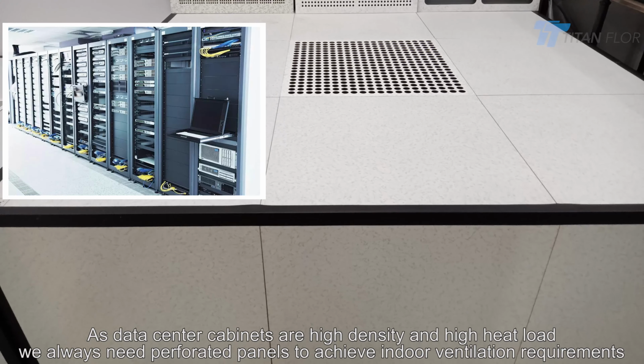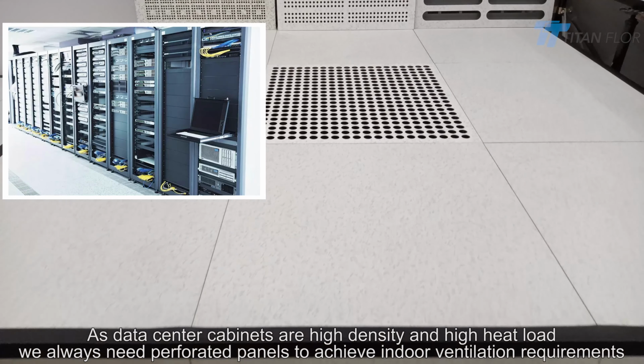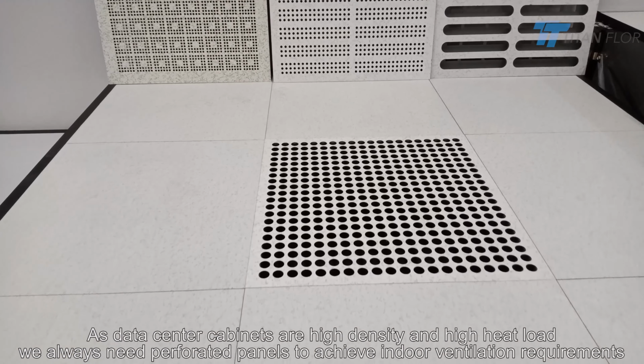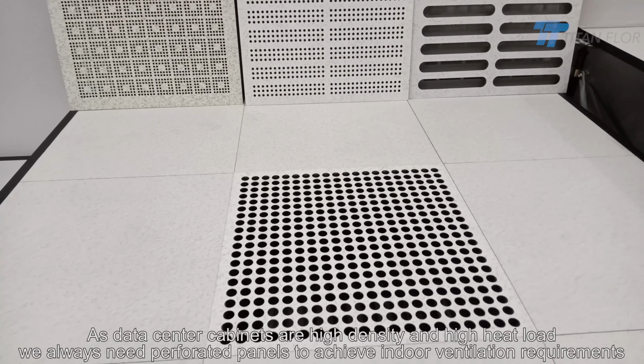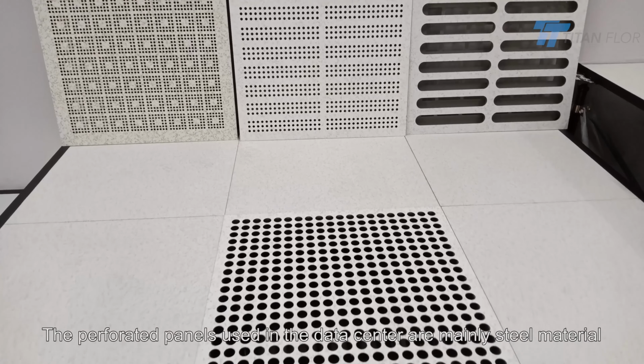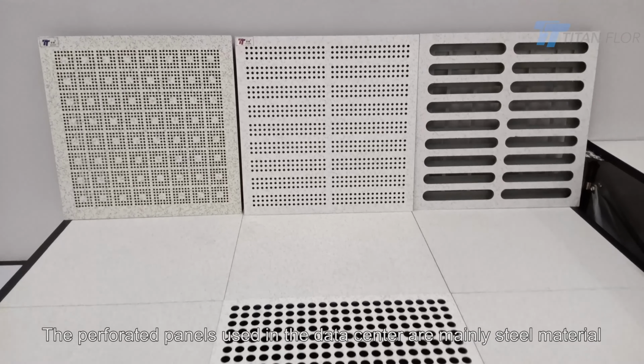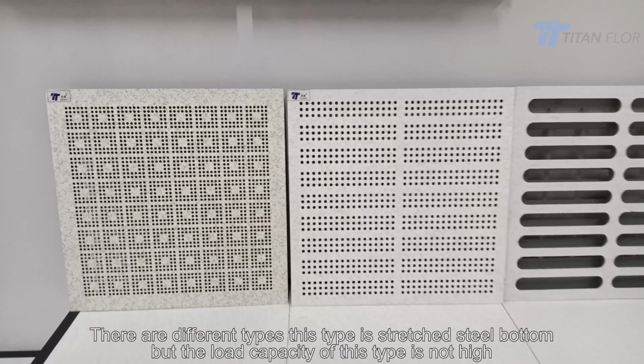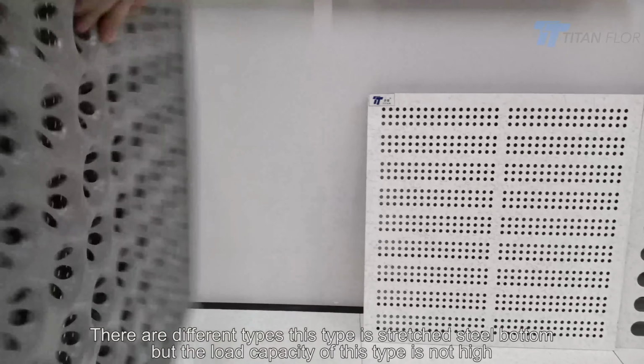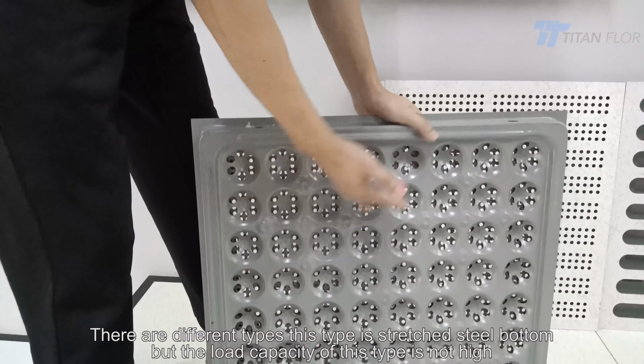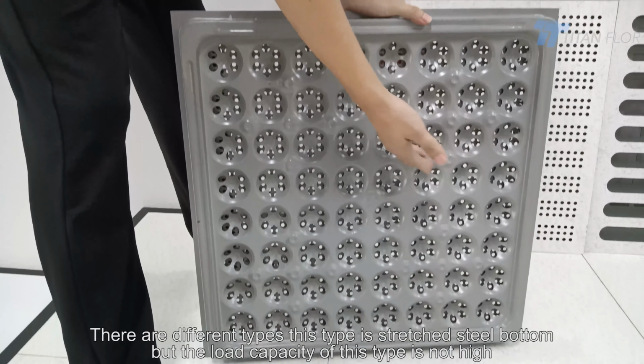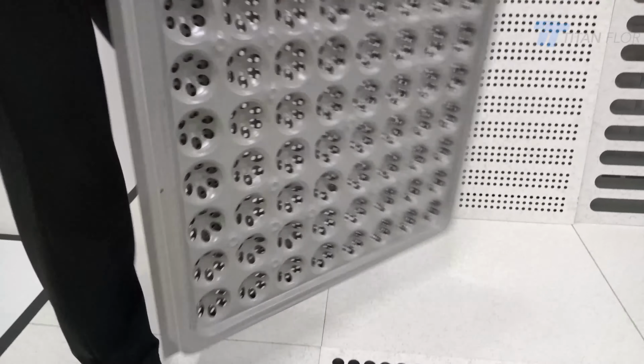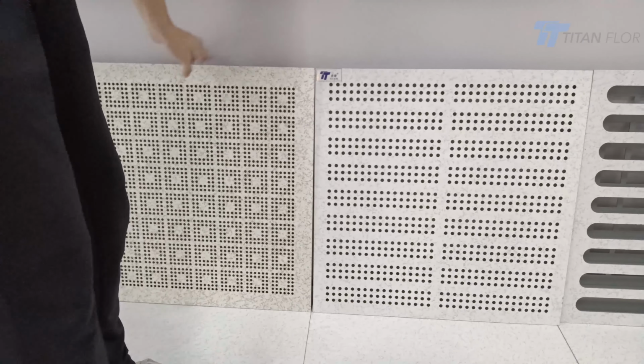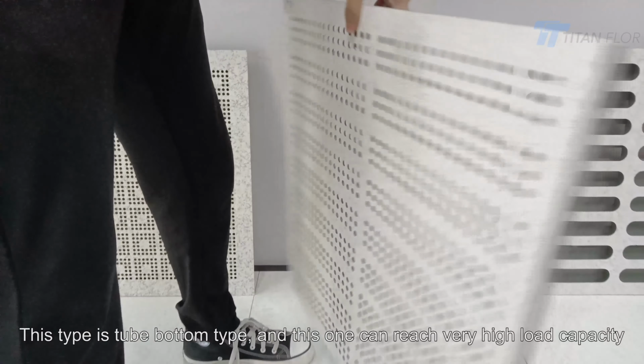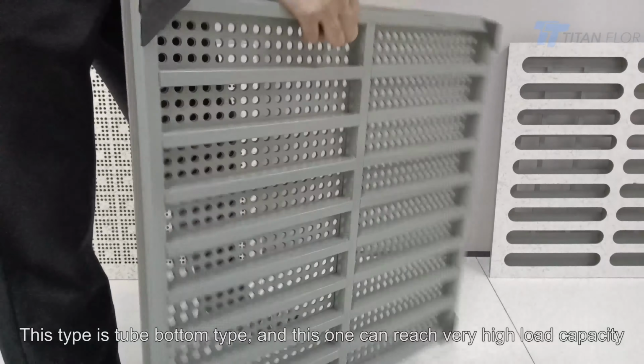As data center cabinets are high density and high heat load, we always need perforated panels to achieve indoor ventilation requirements. The perforated panels used in data centers are mainly steel material. There are different types. This type is stretched steel bottom, but the load capacity of this type is not high. This type is tube bottom type, and this one can reach very high load capacity.